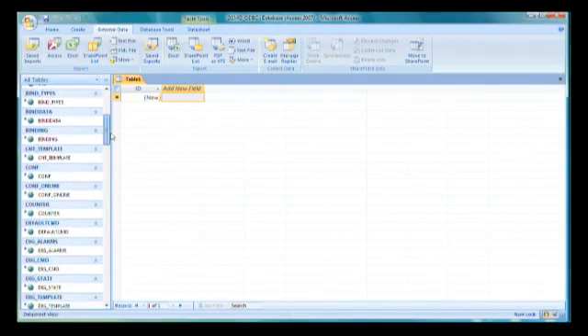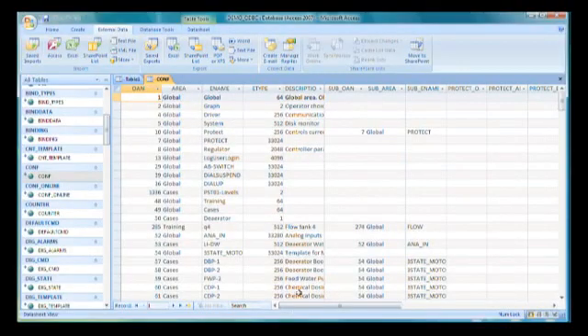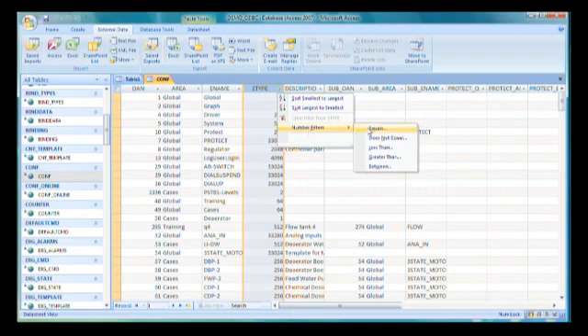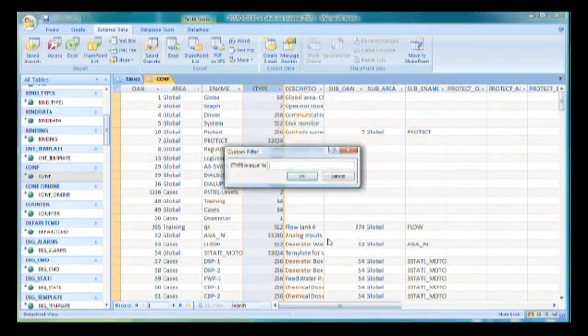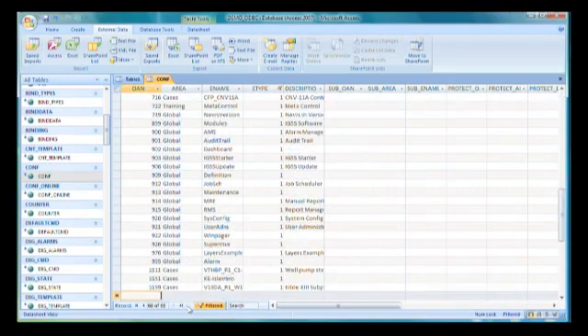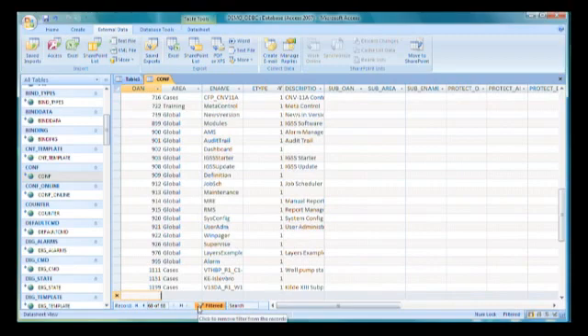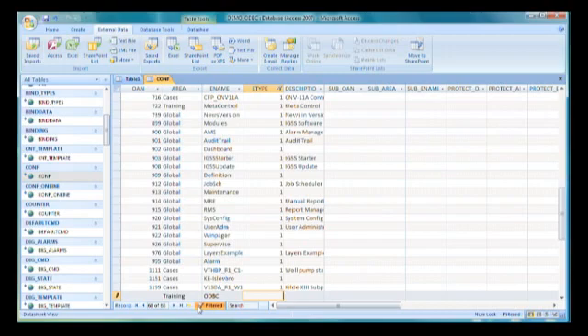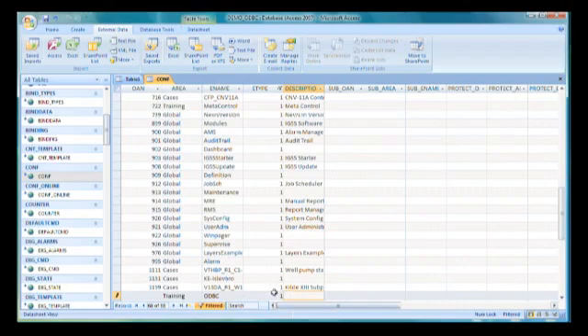We go to the conf table. The conf table is the mother of all, you can say. It's the table where all objects must exist in order to be real IGSS objects. A diagram in IGSS has an object type of 1. If we filter E type equals 1, we get all the diagrams. To create a new diagram, I'll press the new record button. I'll put in training as the area, ODBC as the diagram name, and object type 1 to tell IGSS it's a diagram. We require area, object name, and object type. Then we have a real object.